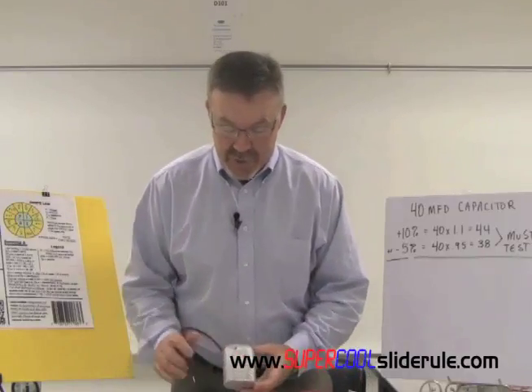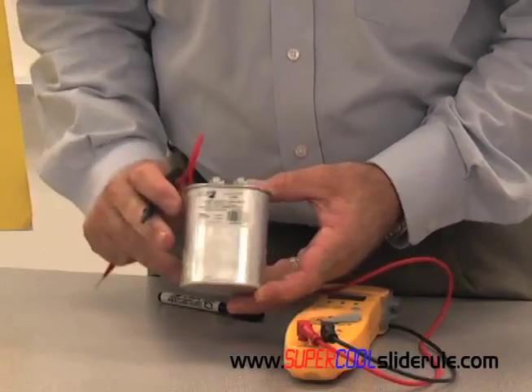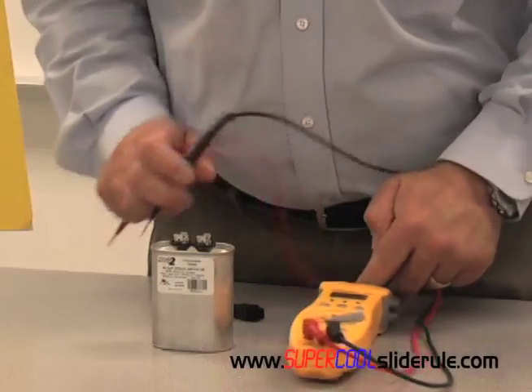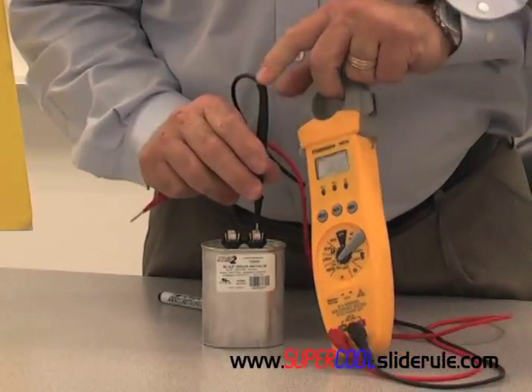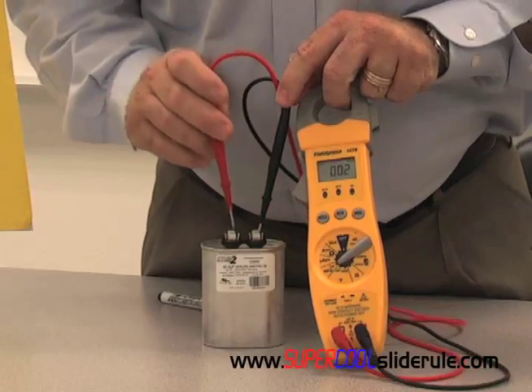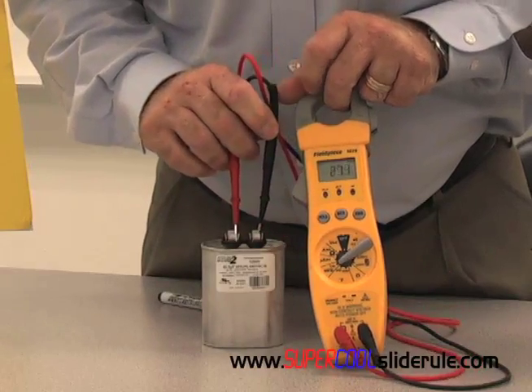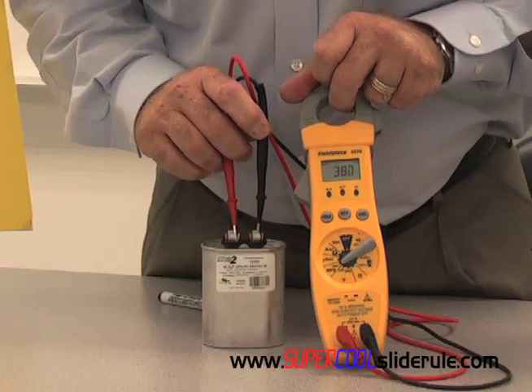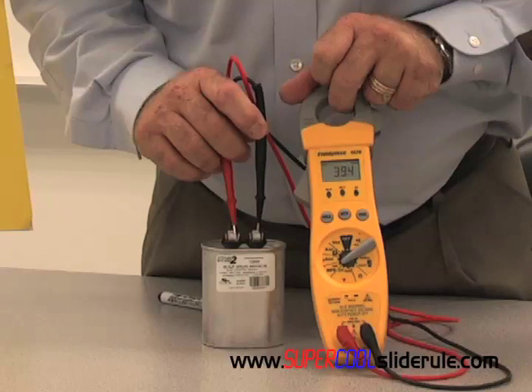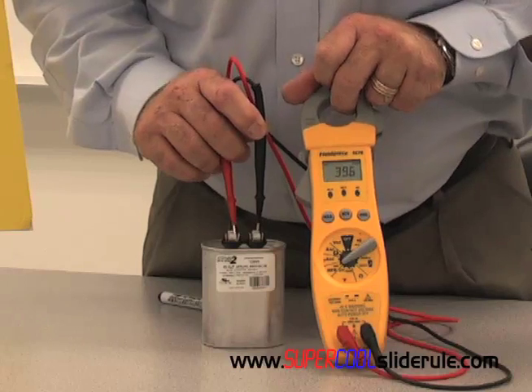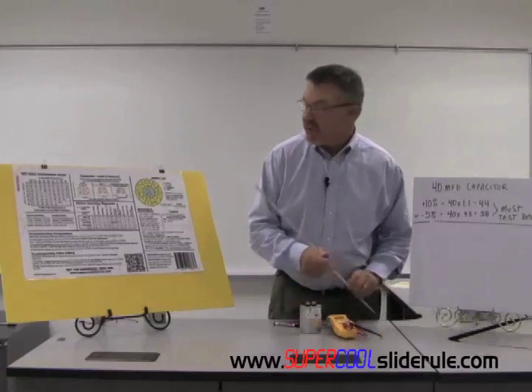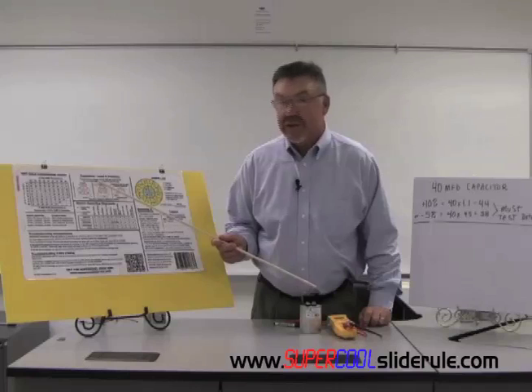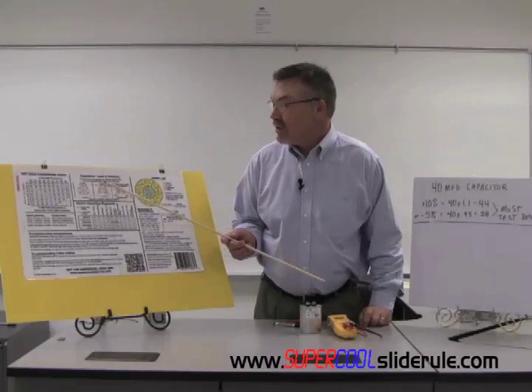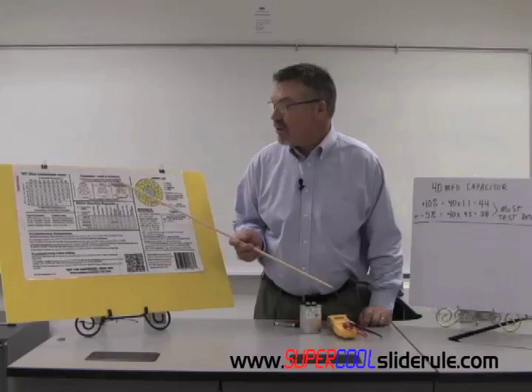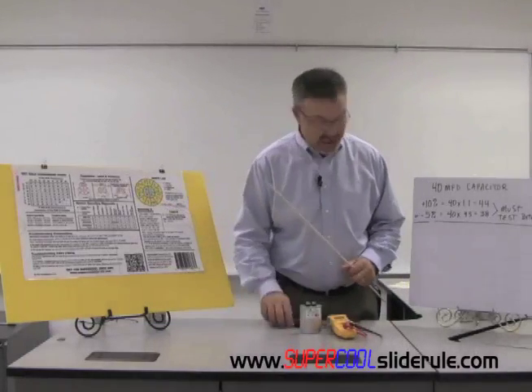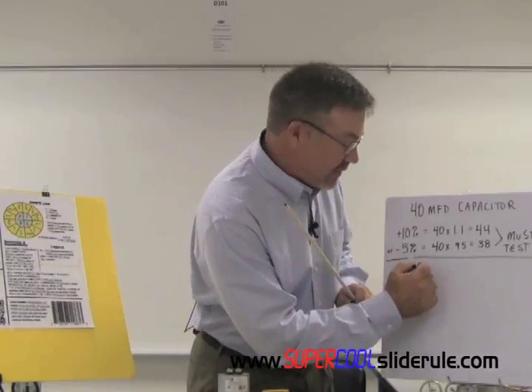Right here I have a 40 microfarad capacitor. To test it, it's very simple. All we do is we put either lead on either terminal. This one is giving us a reading of 39.5. Now, if you refer to your supercool, you will notice that a capacitor can be over by 10% or under by 5%. So we had a 39.5.